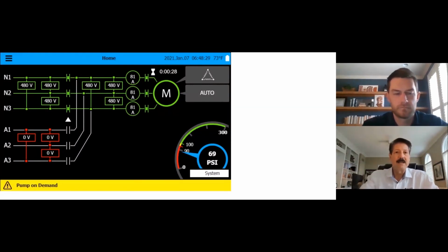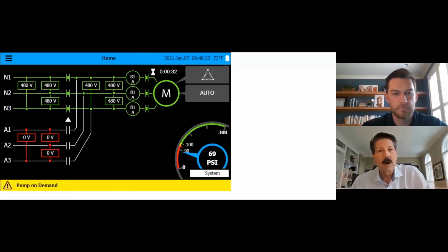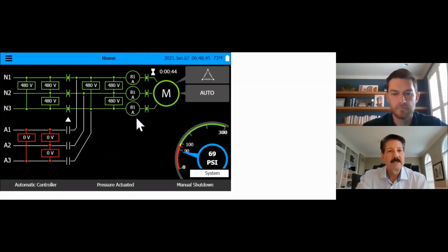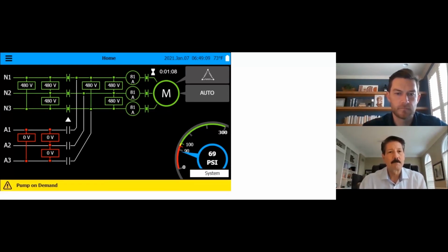And obviously, if you had one that said 81, 42, and 84, you know you have a problem with your B phase there, and it could be an internal short to the motor itself. Degradation of the motor over a period of years or insulation, things like this happen. But it's visual, and it's quite nice to look at this. So when you have a pump on demand auto, there's only a couple reasons why that actually is going to happen. Obviously, I think one of the main reasons is a lot of times the jockey pump controller or pressure maintenance pump, it's tripped offline. So it's not maintaining the pressure, and the main controller turns on as normal leakage occurs. So either it's tripped offline or it's off. It does happen. People turn it off, forgot to turn it back on, and the system kind of slowly works its way down, and the main controller turns on.